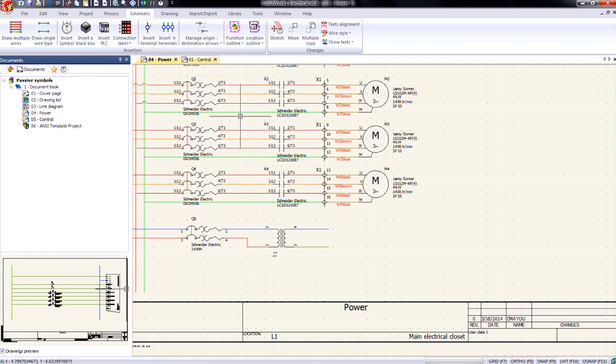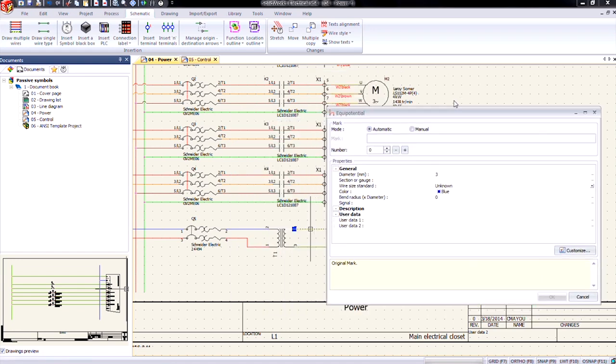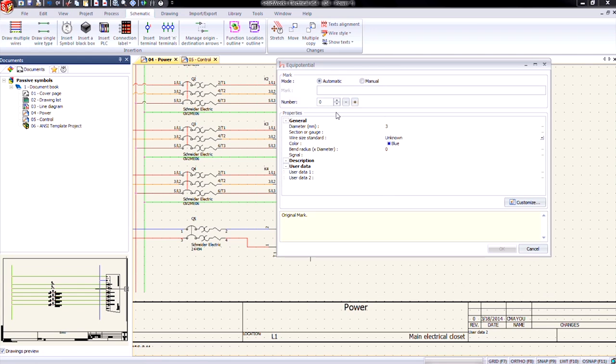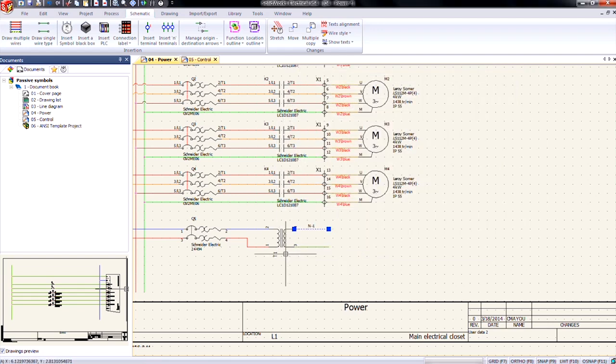Secondly, we need to make sure the equipotential number is the same for each wire. So in this particular case, we're going to set the equipotential for our neutral wire. So let's come in here into the equipotential properties. Just increase it by one, which gives me an N1. I'll go ahead and click OK.